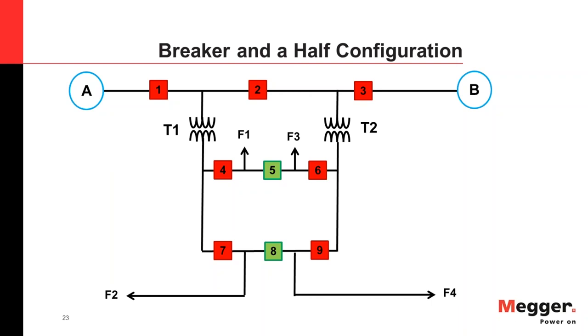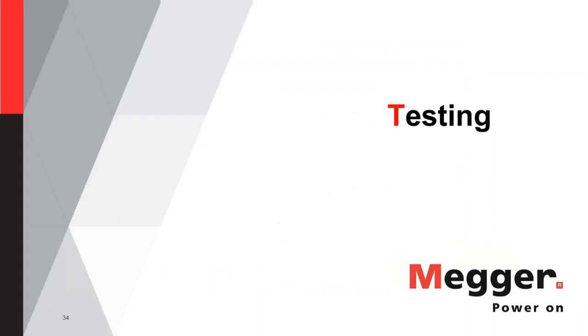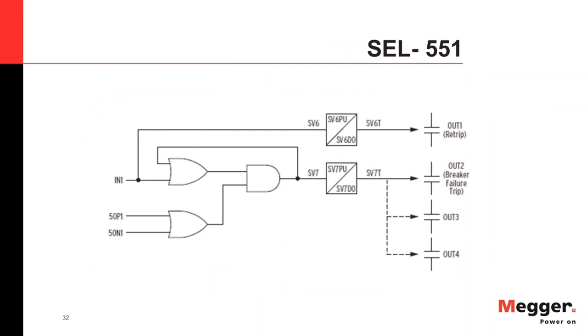Q&A on re-trip timing: The re-trip scheme, as shown in the SEL-551 example, provides a second opportunity for the same breaker to trip before a Breaker Failure is declared. It applies only to breakers with two tripping coils. The first coil fails, and rather than immediately tripping local breakers, the relay energizes the second tripping coil to give the breaker another chance to clear the fault.